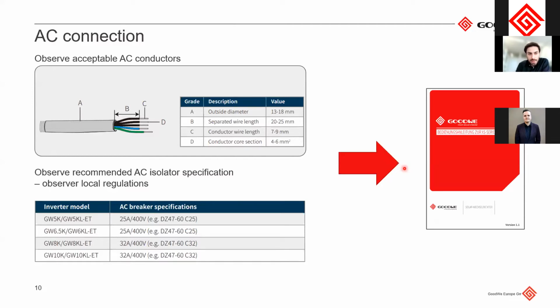It's also good to check the AC connection. And here it also differs from inverter to inverter. Please check the cable sizes and the conductor sizes to make sure that they have the right diameters. This is important because in some cases you won't fit the conductors into the sockets that you use on the inverters if it's not the correct size. Also observe the AC isolator specification. It's recommended to use some kind of AC breaker. Please make sure that you have a correct AC breaker that can hold the current in the cables that you install.